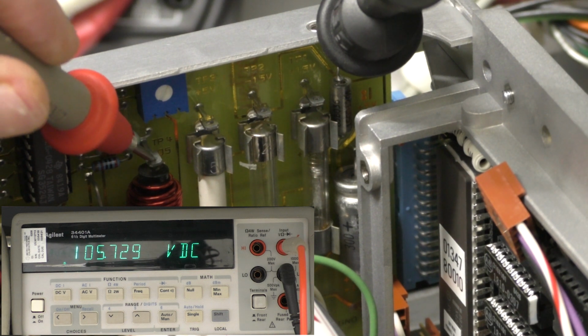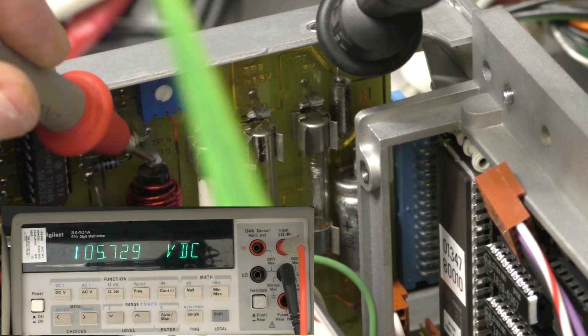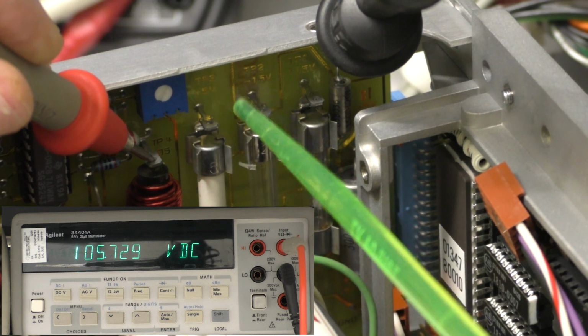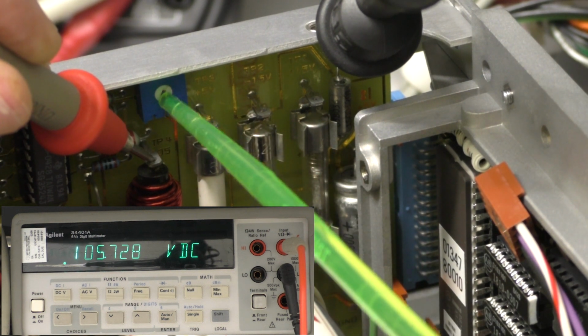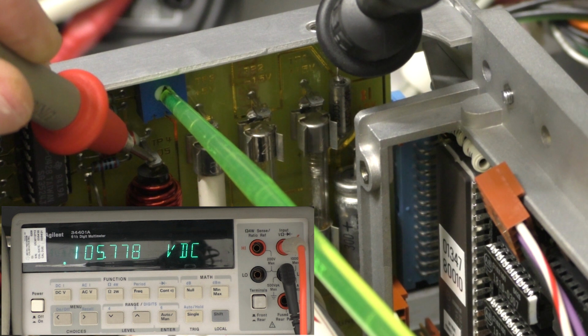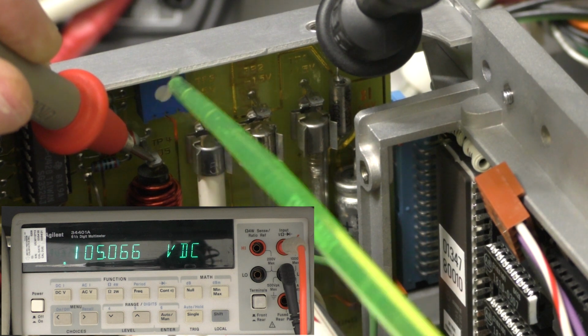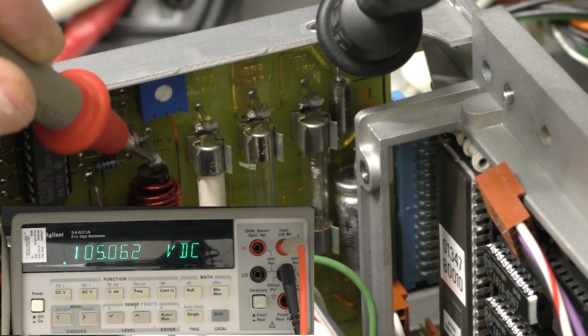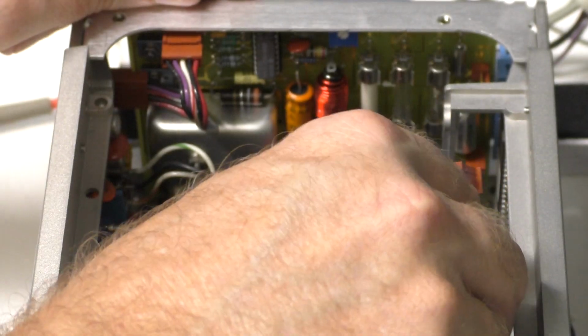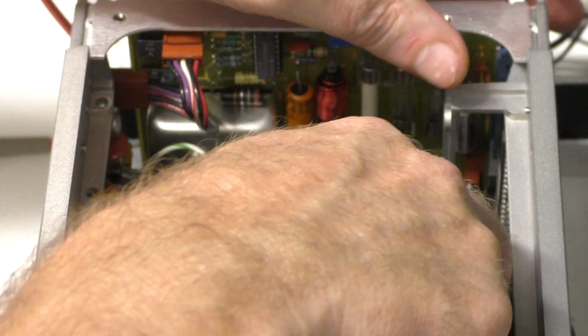Now we will check and adjust TP4. This is the supply to the A4 high voltage board. It must be 105 volts ±250 millivolts. It's high at 105.729 volts. Adjust R10 to get the voltage into spec. 105.06 volts is well within spec. Power down, and wait for supply to fully discharge.